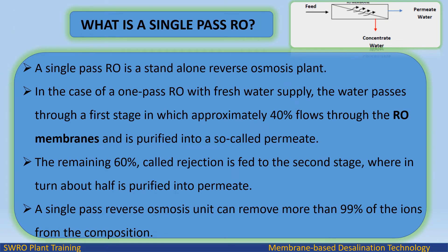A single pass RO is a stand-alone reverse osmosis plant. In the case of a 1 pass RO with fresh water supply, the water passes through a first stage in which approximately 40% flows through the RO membranes and is purified into a so-called permeate. The remaining 60%, called rejection, is fed to the second stage, where in turn about half is purified into permeate. A single pass reverse osmosis unit can remove more than 99% of the ions from the composition.